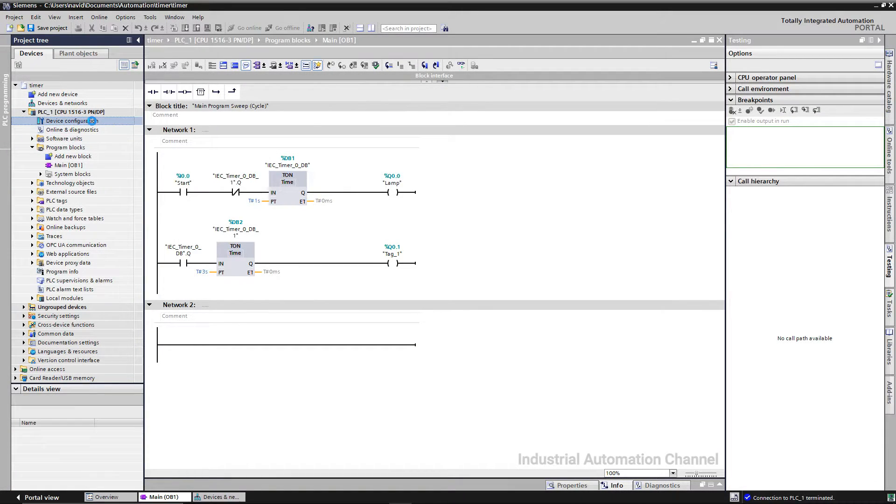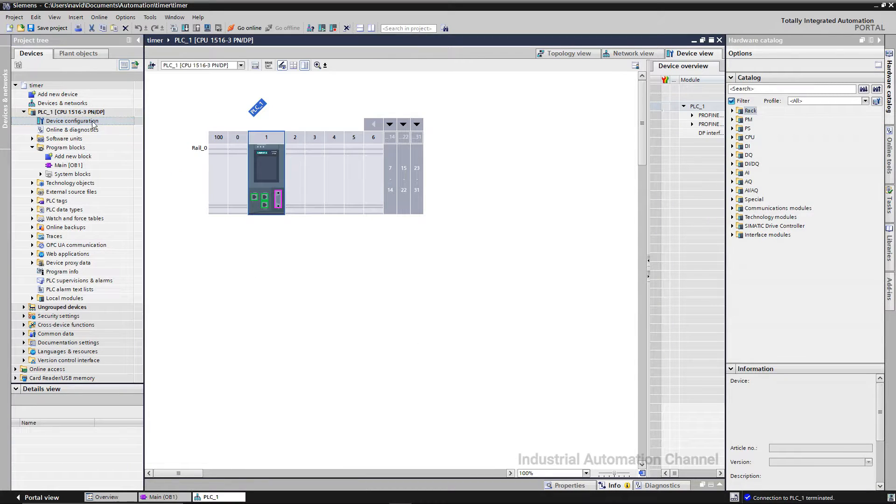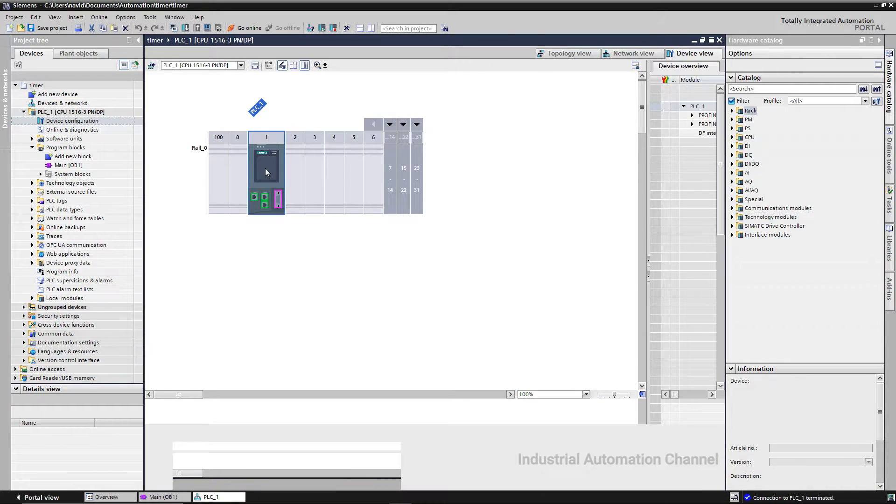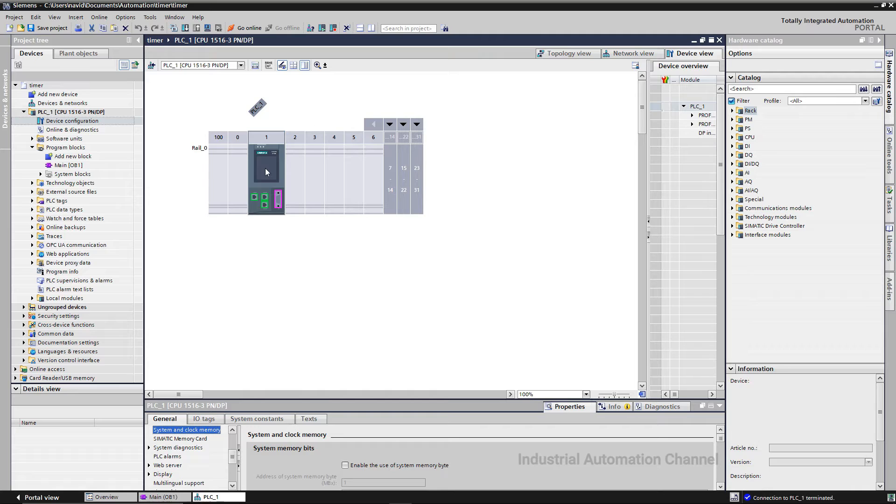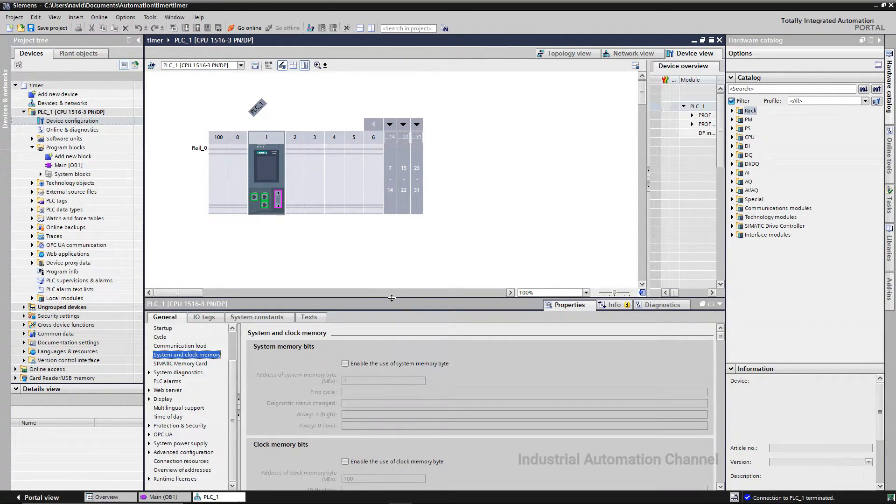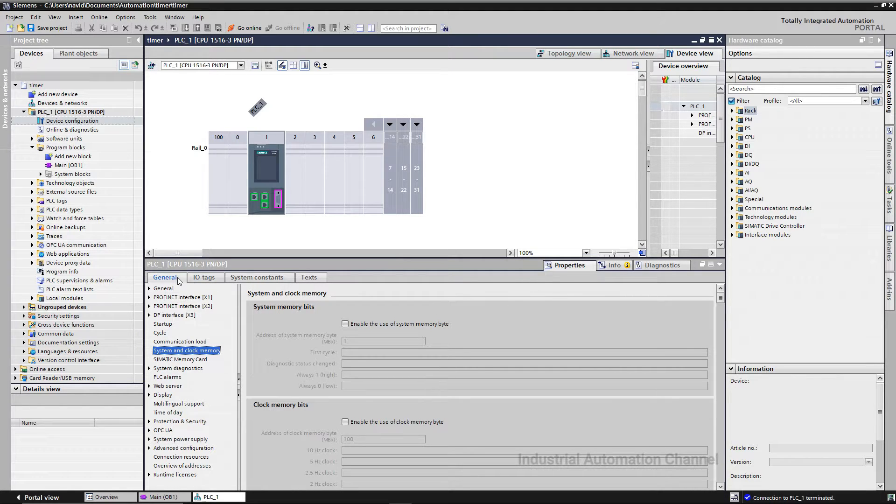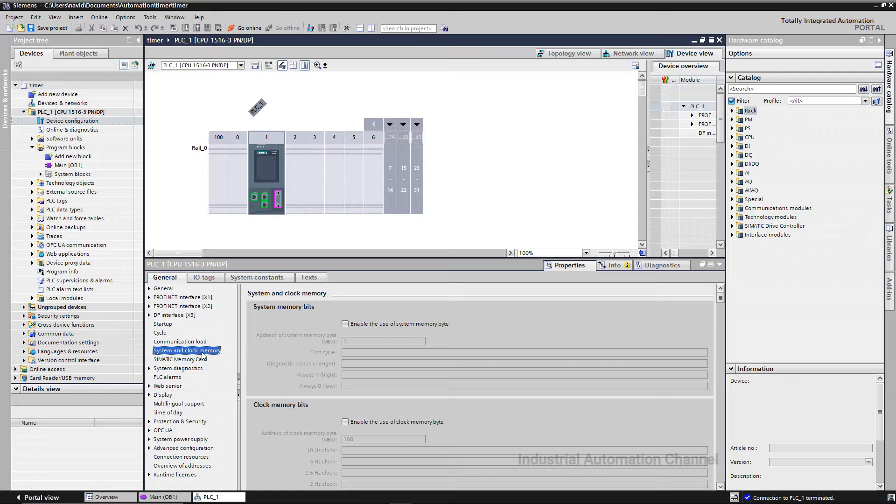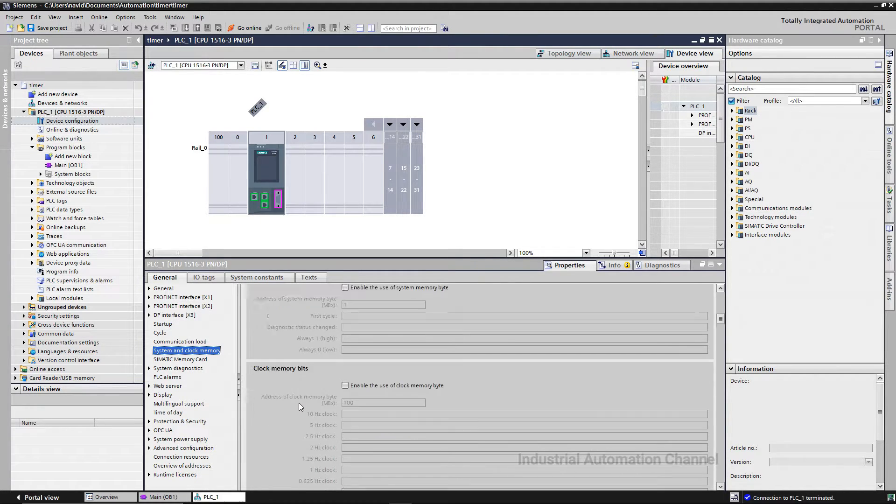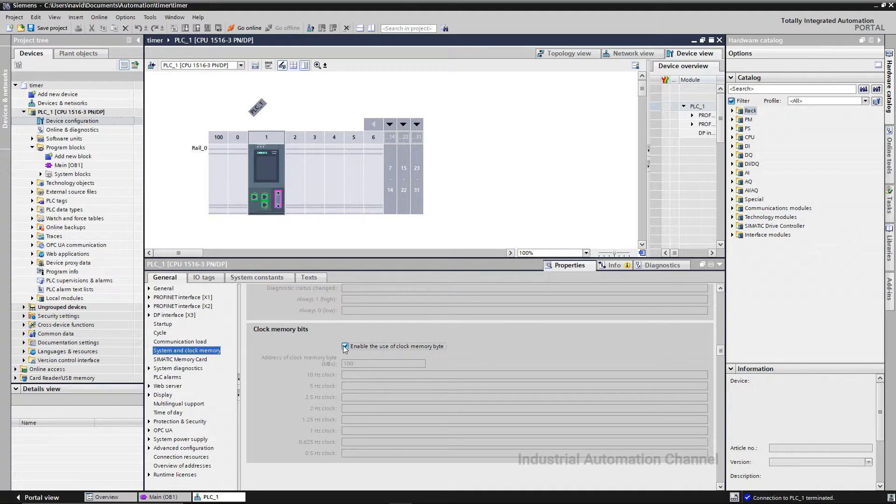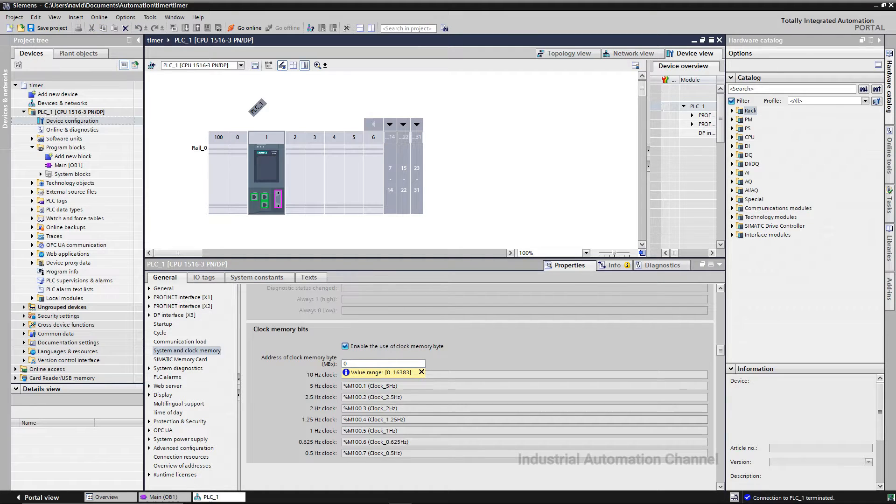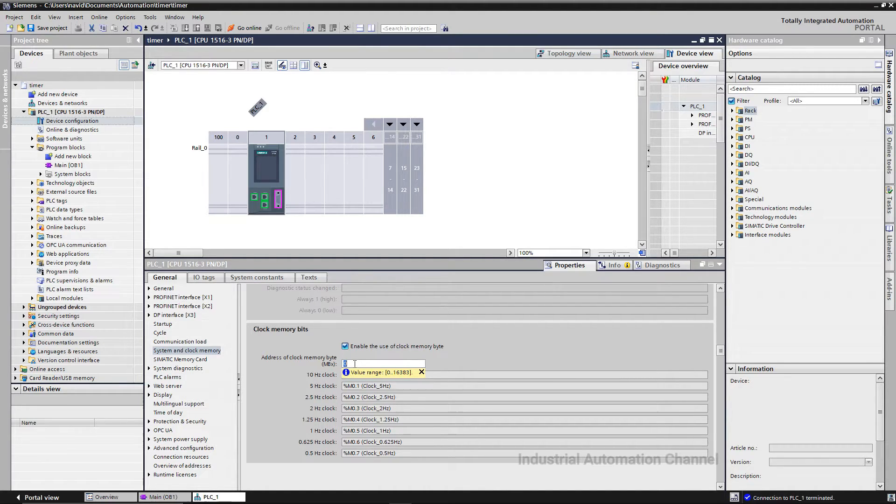What we need to do is clicking on device configuration and then on the PLC here. From the properties and general you see system and clock memory, then we see clock memory bits. If you want to use it, you need to enable it by clicking here. Now it's enabled. Here we can give our desired address, which byte you want to use. You can use whatever you want.